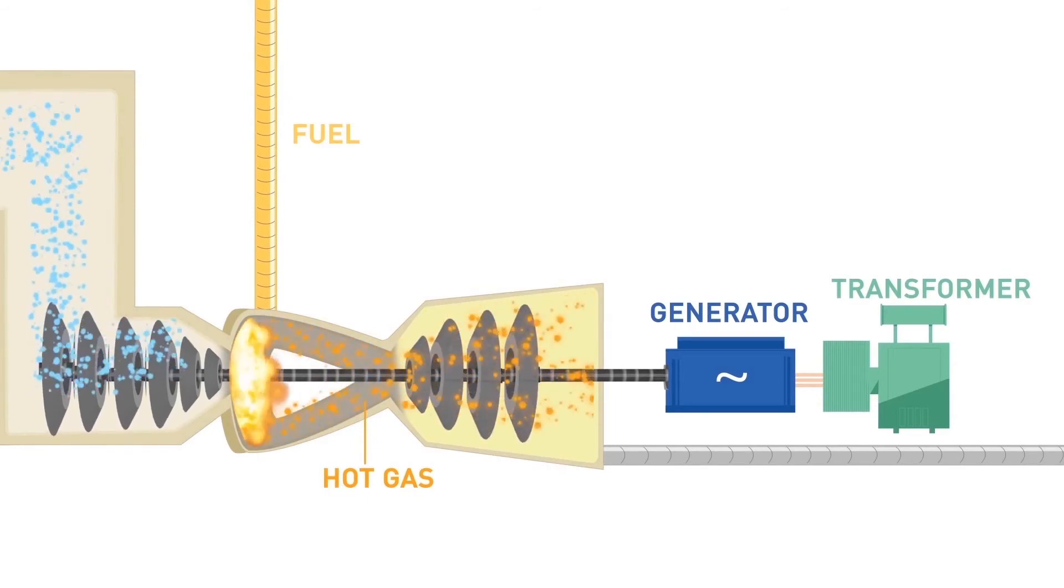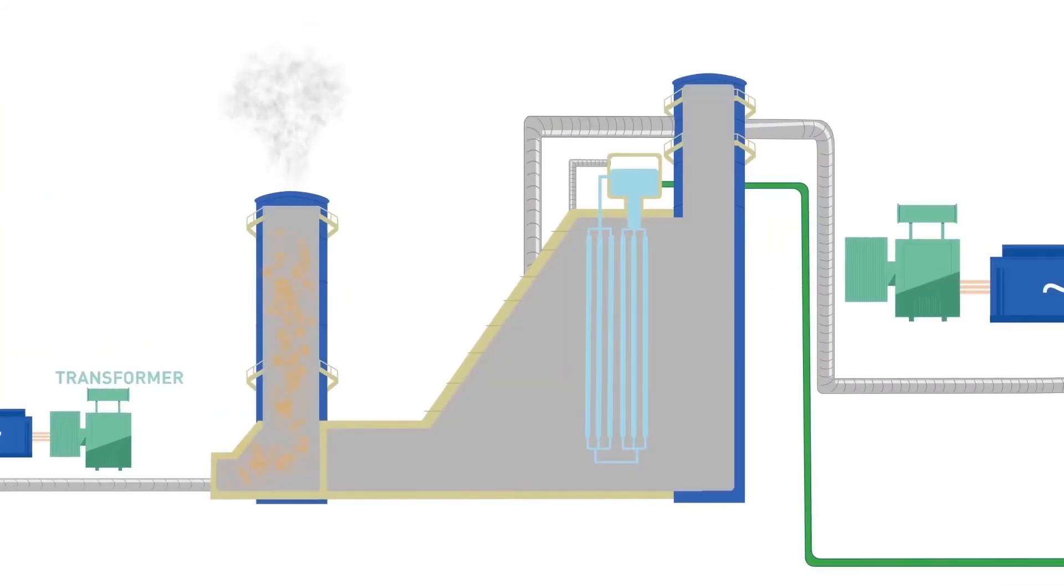In simple cycle operation, the exhaust gas from the gas turbine is expelled into the atmosphere. However, to maximize efficiency, this waste heat is diverted via a diverter damper to a heat recovery steam generator (HRSG), which is essentially a boiler responsible for converting demineralized water into steam.